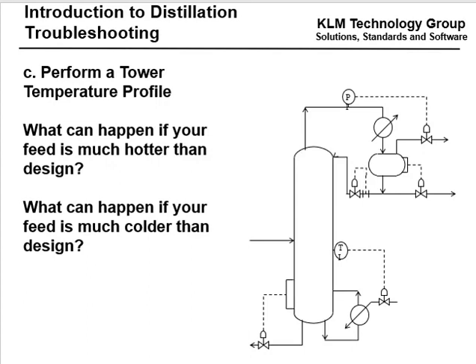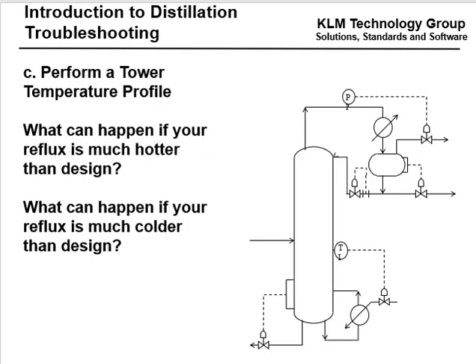What happens if your feed is much hotter than design? Normally we want the feed to be about 50% vaporized. If it's much hotter, it may be 100% vaporized and the few trays above the feed could be flooding. If the feed is much colder than design and all liquid, you could flood the few trays right below the feed. What happens if your reflux is much hotter than design? You want the reflux to come in, condense, cool the liquid on the tray, and go down the column. If it's much hotter, you can build up an artificial recycle around the top of the column and not have enough reflux. If your reflux is much colder than design, it can condense too much vapor and actually flood the top of the column.